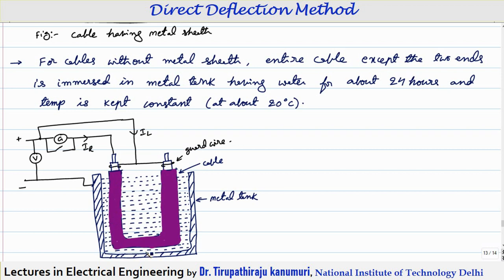The saline water is touching the insulation — this acts as the metallic sheath part shown before. The outer insulation at both ends is stripped and those stripped ends are connected together, acting as a guard wire. Whatever leakage current is there will directly pass through this guard wire.